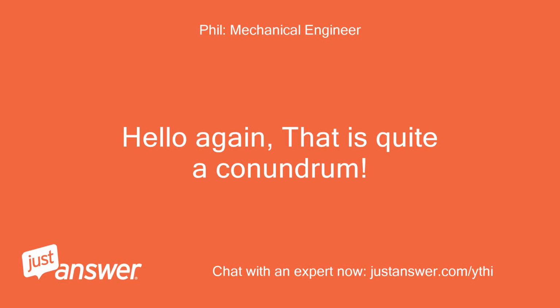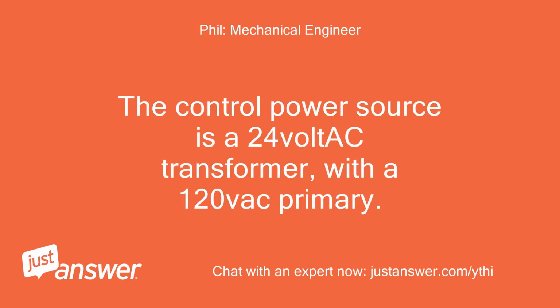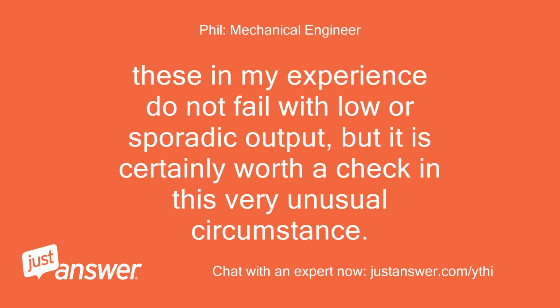Hello again, that is quite a conundrum. The control power source is a 24-volt AC transformer, with a 120-VAC primary. These in my experience do not fail with low or sporadic output, but it is certainly worth a check in this very unusual circumstance.